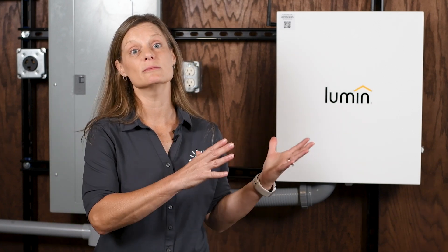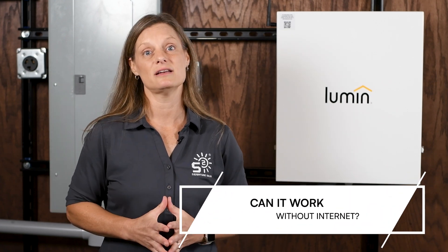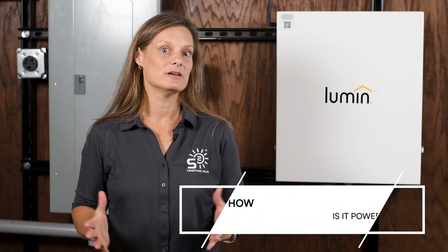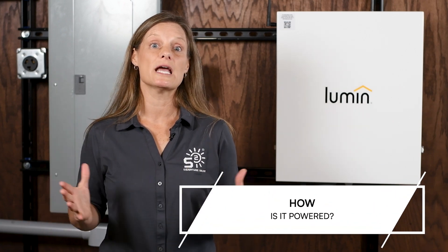Let's address some common questions about the Lumin Smart Panel. Can it work without internet? Yes — the panel settings are stored locally, so you don't need cloud connectivity for basic operation. However, initial setup, historical data, and advanced features require an internet connection. Is it compatible with all systems? The panel is designed to work seamlessly with any backup system, whether a generator or battery. It currently integrates state of charge information from Enphase, SolarEdge, and Tesla, with more partners on the horizon — including EG4 batteries. How is it powered? The panel is powered by a 15 or 20-amp dual pole breaker and has a low standby wattage of 6 watts. Even with all relays running, it only uses around 50 watts.